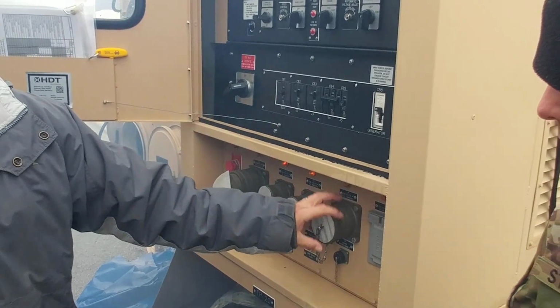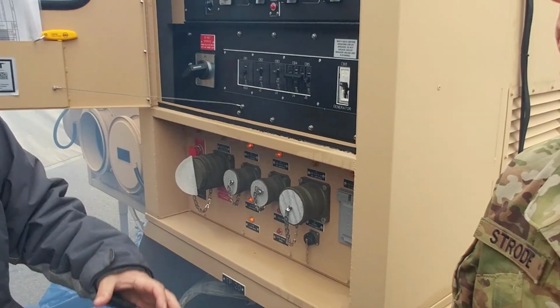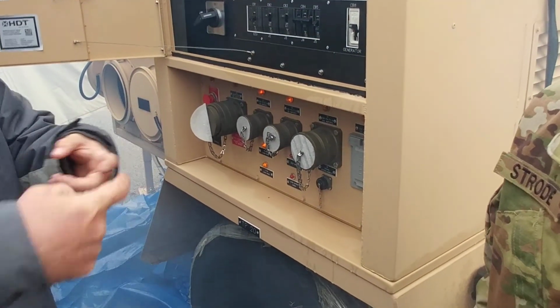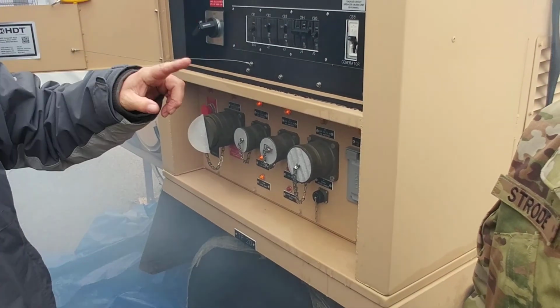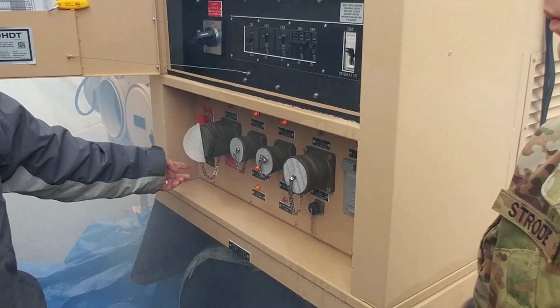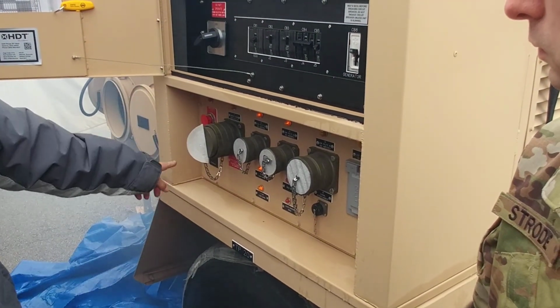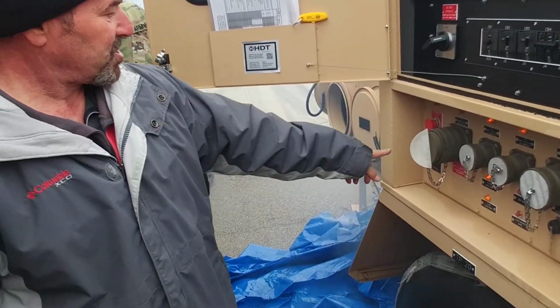Because that's your main breaker, that's your main big one. That's if you're going to parallel them - parallel this one with that one to get 70 k's of power. You can do parallel, or that's to be on single.